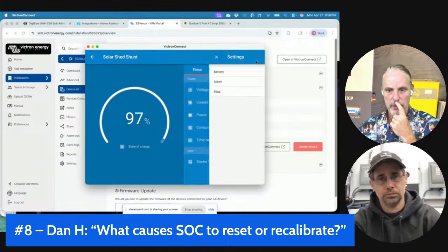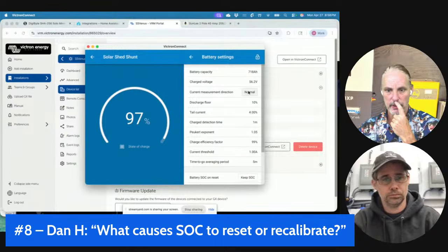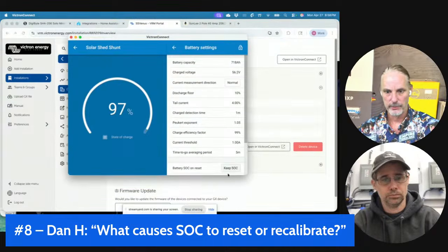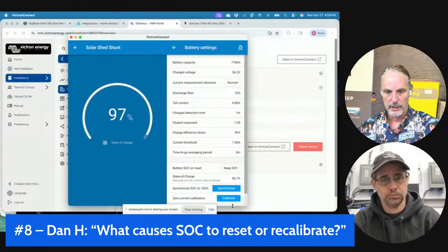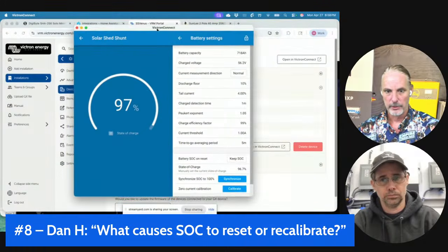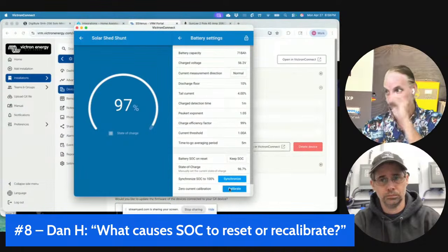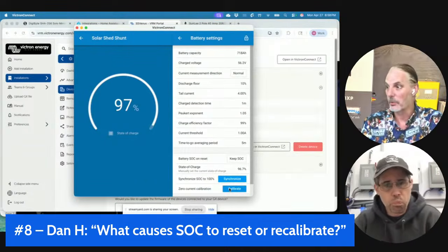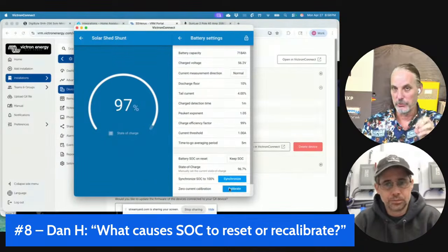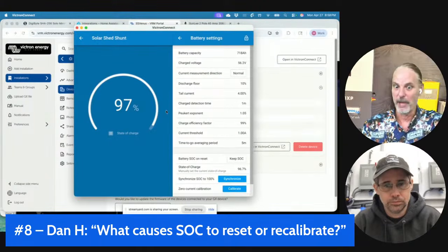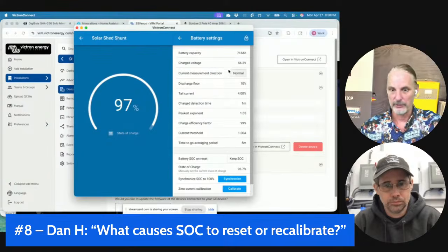So in here you can go in and set up under the configuration. And what I was saying earlier about calibrating, you can set calibration to 0, meaning there are 0 amps running through this right now, and that makes it much more accurate. But my suggestion is don't just assume there's 0. Disconnect everything from one of the sides, flip the power off where the system is truly off and it's 0, and the only thing powered up is this item. Otherwise it won't be as accurate as you think. That little bit of butterfly effect makes a big difference.